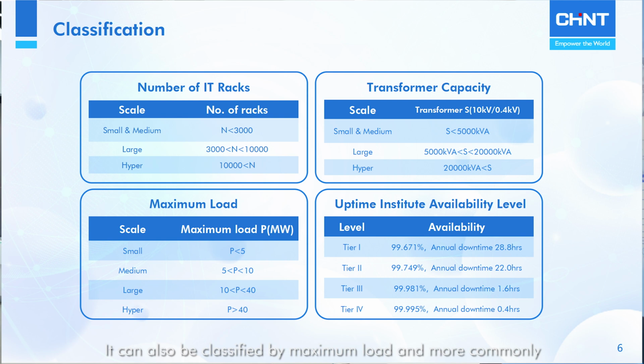It can also be classified by maximum load, and more commonly, it is classified by the tier level: tier 1, 2, 3, and 4. These are all down to the availability. 99.671%, for example, is a tier 1, a very basic data center, and it has an annual downtime of up to a maximum of 28.8 hours, just under a day.